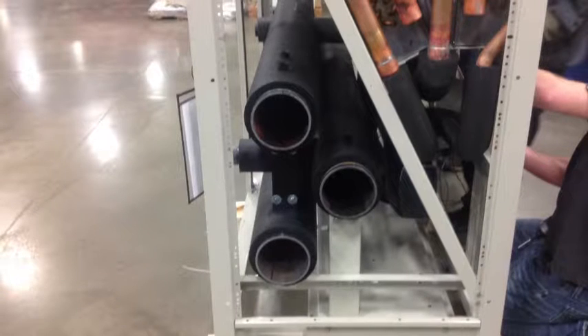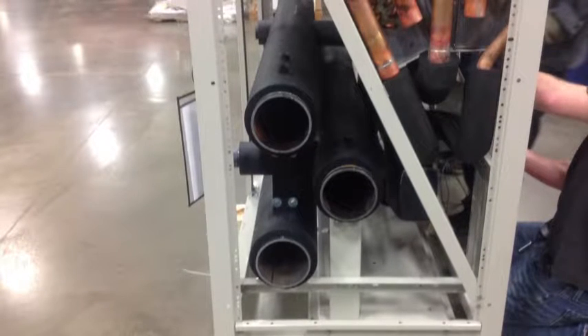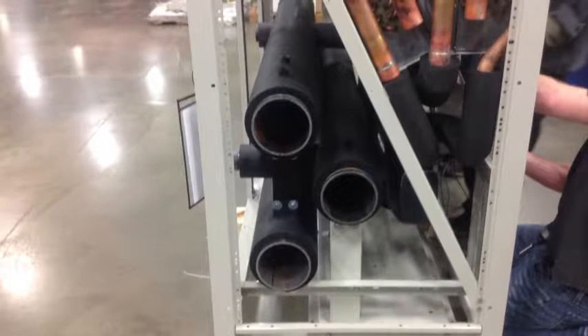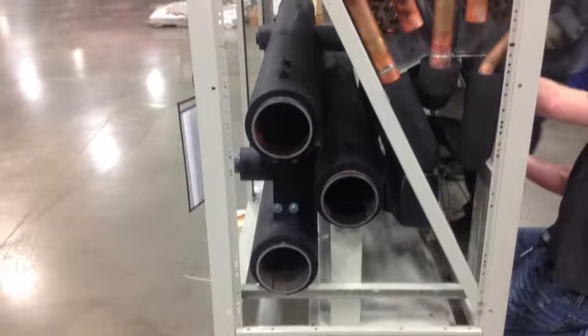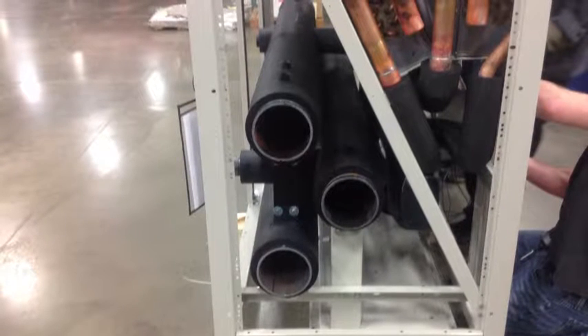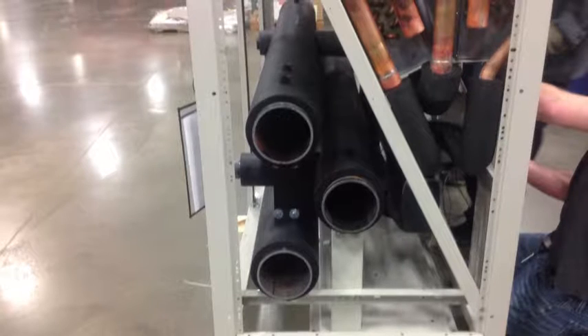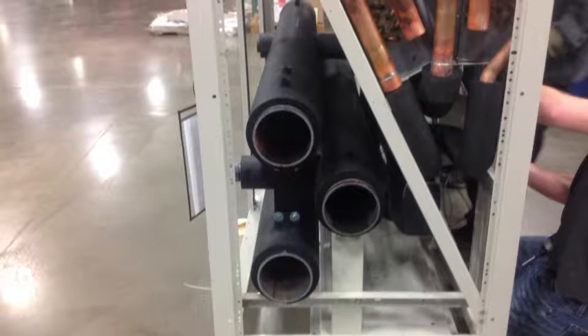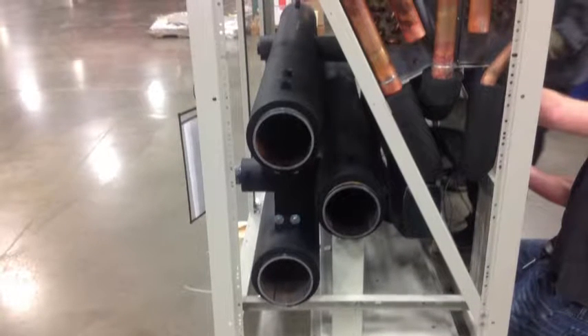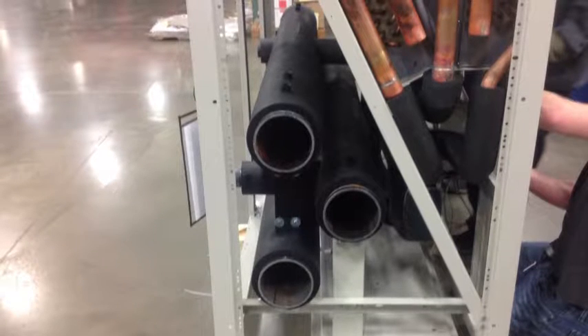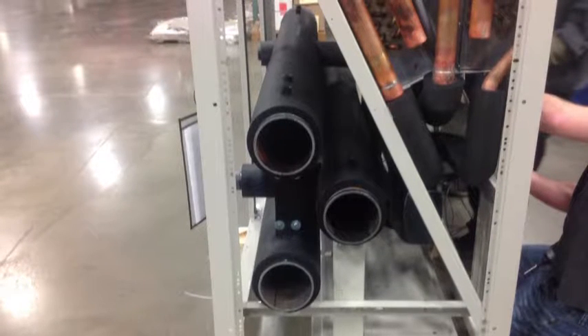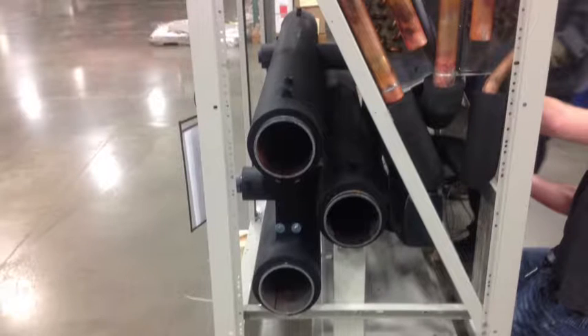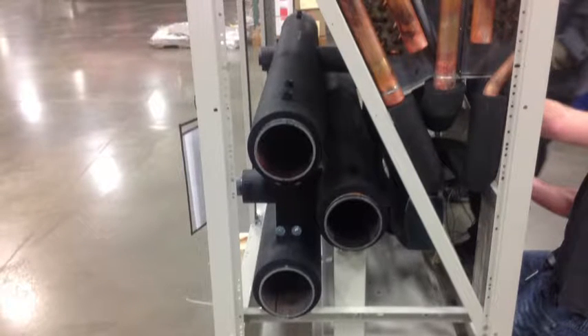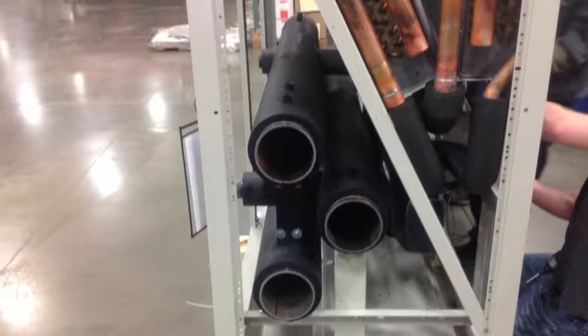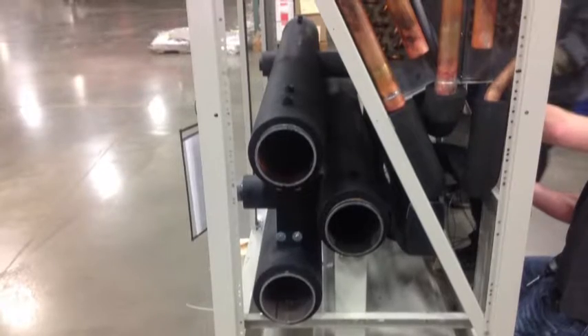There are 3 headers in a free cooling module. The one that is offset to the right is the entering water header. Water goes from that header up into the coils where the cooling occurs, and then down into the top of the 3 headers to enter the mechanical modules. The bottommost header, directly underneath the header that goes into the mechanical modules, brings leaving chilled water back from the mechanicals through the free cooling and ultimately out into the leaving connection from the entire array.